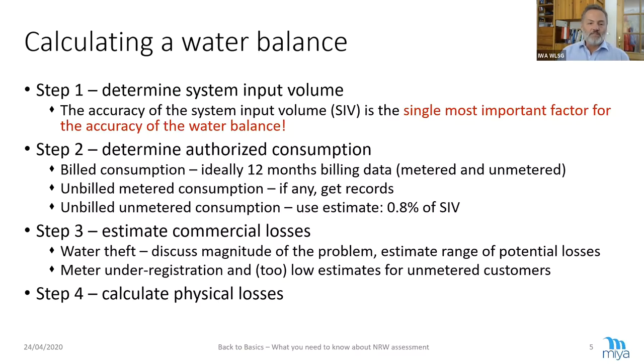How do we calculate the water balance? The first step is we determine the system input volume. This sounds very trivial — read the water meter — but very often we don't have the water meter, or we have only some water meters, not for all our sources. The meters are old, the meters are not working. But the system input volume is the single most important factor for the accuracy of the water balance. We always have to remember this.